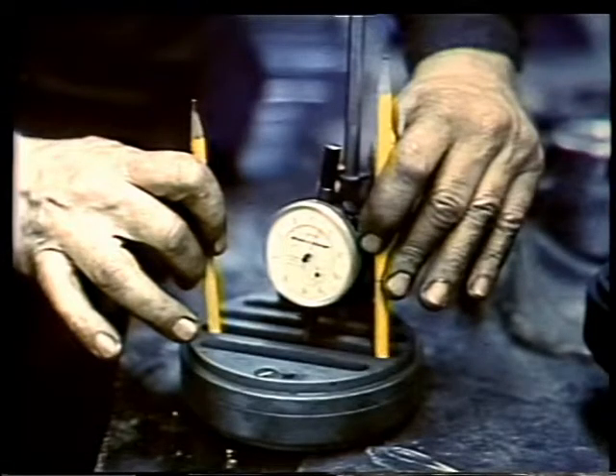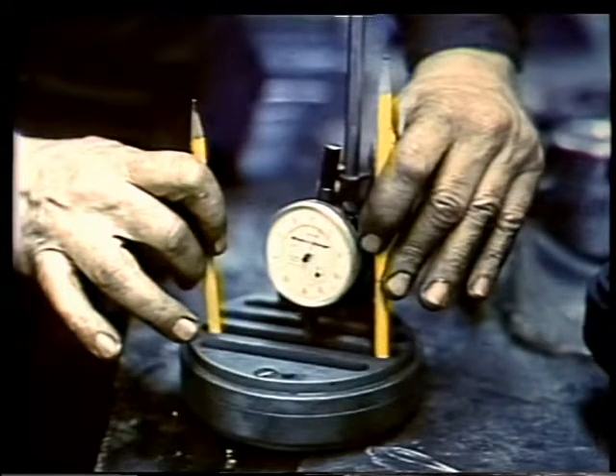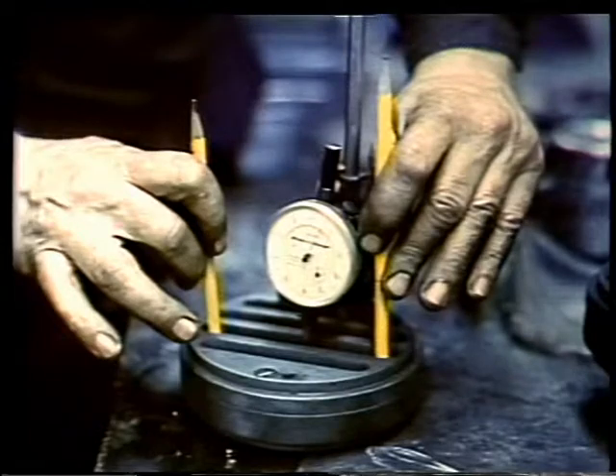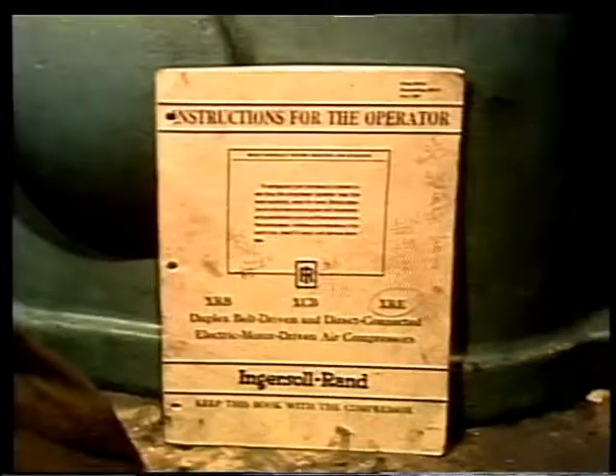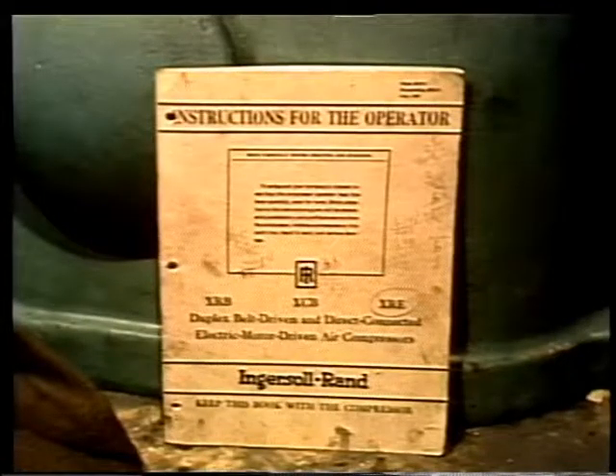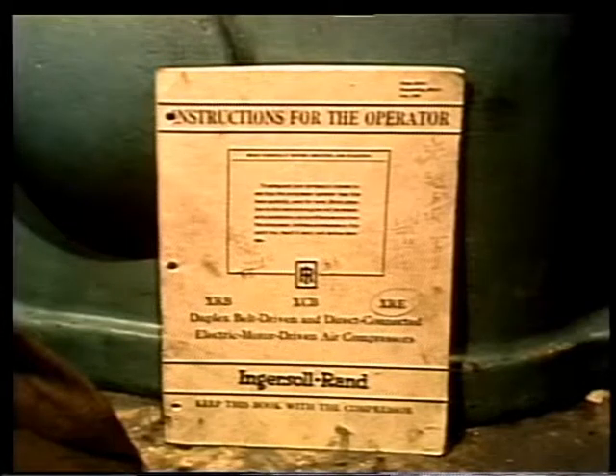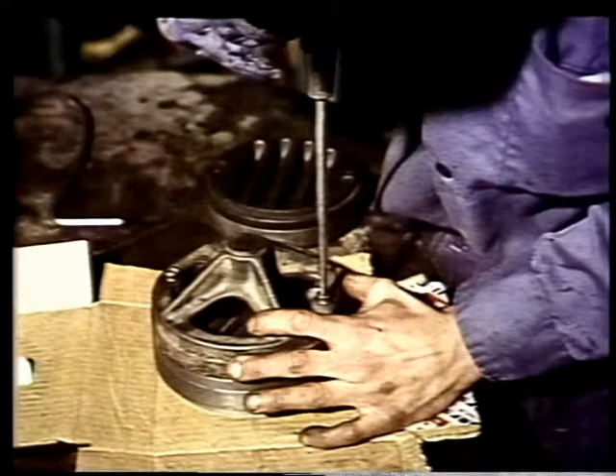Slowly press down on the channel, forcing it open. Be careful not to bump the valve or the indicator. The amount the indicator moves indicates the lift of the channel. If the lift of the channel is not within the range of specifications set in the manufacturer's manual, you have two choices. You can either replace the valve or machine the step that the valve seat sits on. After you've reassembled the valve, the next step is to refasten its inner cover.